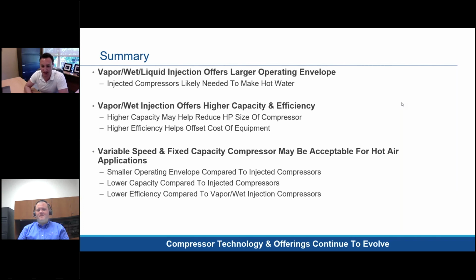First is, does the liquid injection not slug the compressor a little? It shouldn't, because it's a small amount of liquid that they're dropping in there at that point. So it's not a reliability concern, and it's controlled by the compressor controls itself. So the compressor kind of owns how much liquid is coming in to the compressor at that point. So there's some liquid in there, but it's not enough liquid to push the oil off of the scrolls and cause lubrication issues.